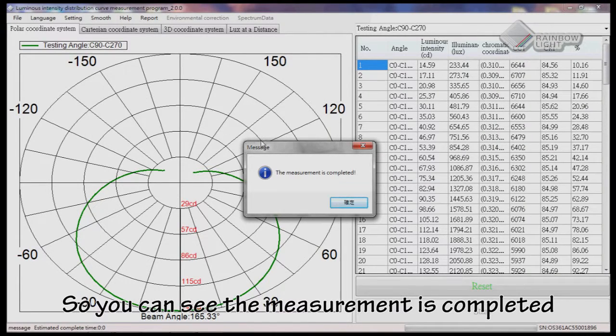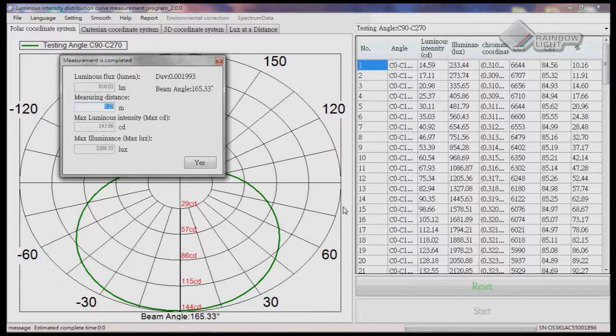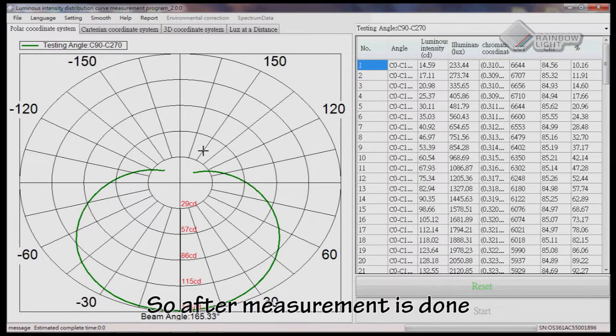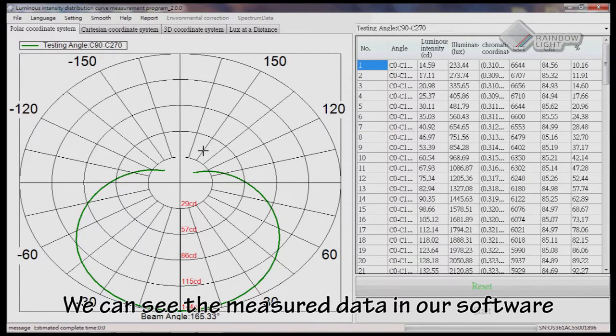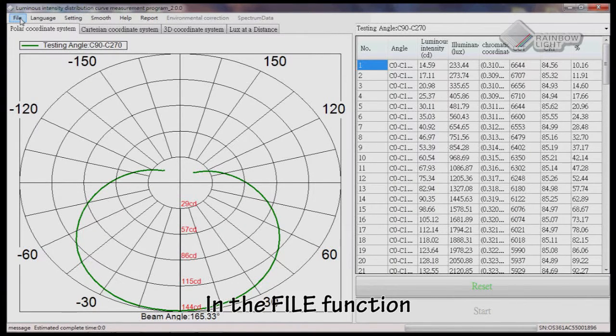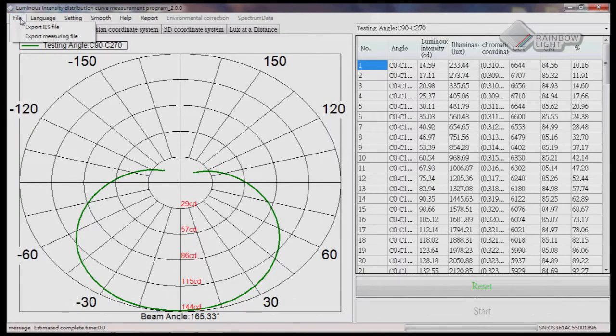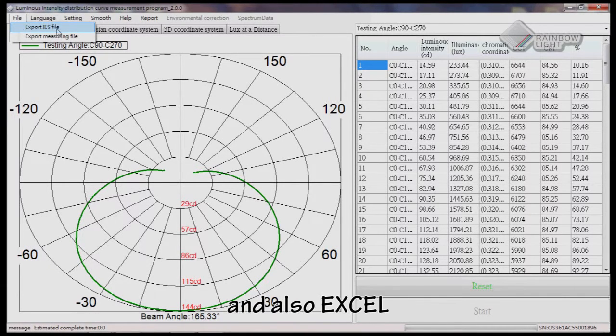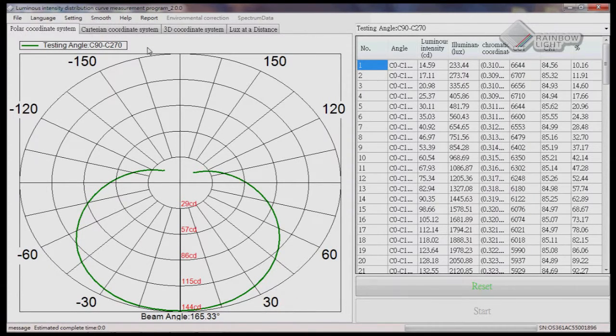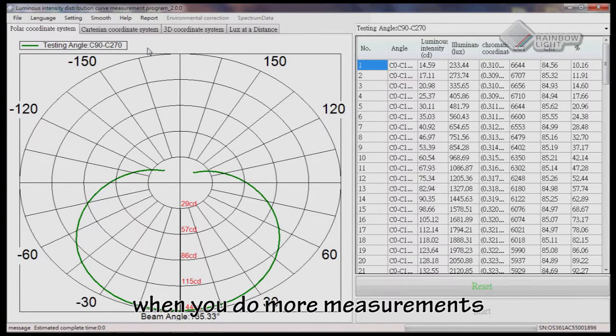As you can see, the measurement is completed right now — just click yes. After the measurement is done, we can see the measured data in our software. In the file function, the data can be exported to IES file and Excel. The data will be more precise and smoother when you do more measurements.